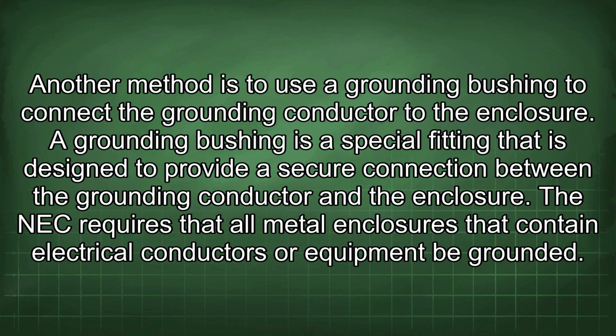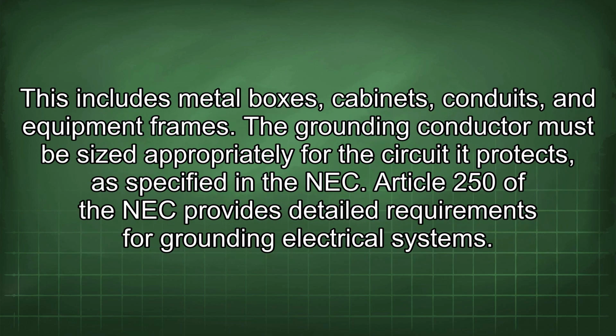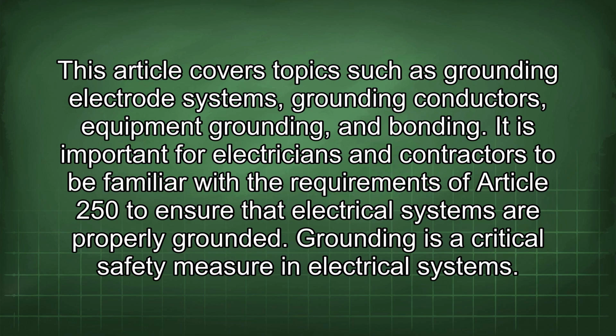The NEC requires that all metal enclosures that contain electrical conductors or equipment be grounded. This includes metal boxes, cabinets, conduits, and equipment frames. The grounding conductor must be sized appropriately for the circuit it protects, as specified in the NEC. Article 250 of the NEC provides detailed requirements for grounding electrical systems. This article covers topics such as grounding electrode systems, grounding conductors, equipment grounding, and bonding. It is important for electricians and contractors to be familiar with the requirements of Article 250 to ensure that electrical systems are properly grounded.